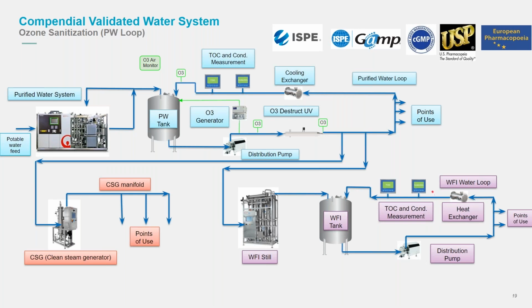Like the purified water system, we have our critical instruments on the return line. One thing of note, and we'll show it on one of the slides, is that the water for injection treated water quality changes from purified water. The conductivity and the TOC remain the same, but what changes is that the bacterial requirements are much tighter. We're looking at less than 10 CFU per 100 mL. And then we have a fourth parameter, which is endotoxins. We're looking at removing to less than 0.25 EU per mL. So it's much tighter in terms of microbial limits here, which you would expect for things that are going to go directly into your bloodstream, or parenteral products.